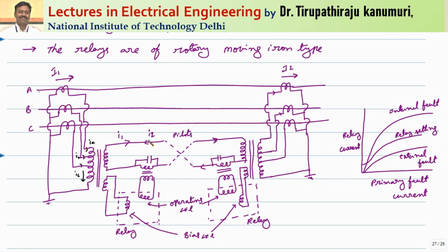So as both the currents are in the opposite direction, this is called current balance protection. Under normal operating conditions, the net circulating current in the secondary will be equal to 0. In a similar way, depending on the value of the primary current I1, the current will be induced in the secondary, and this will pass through your biased coil.